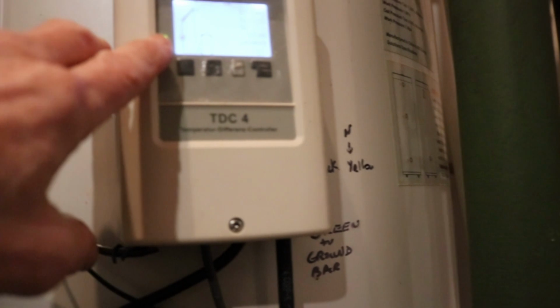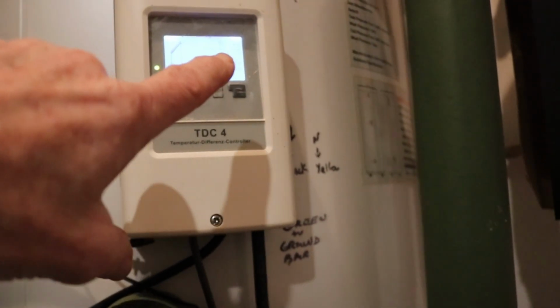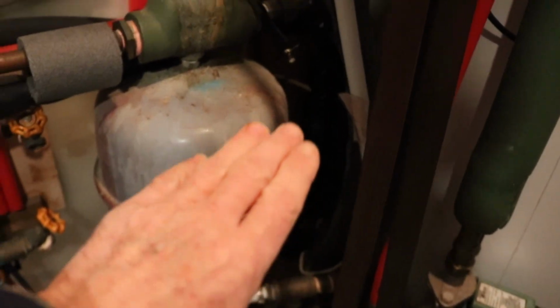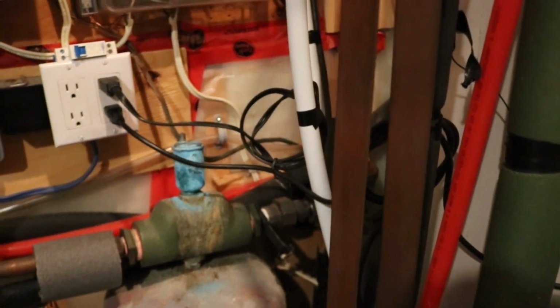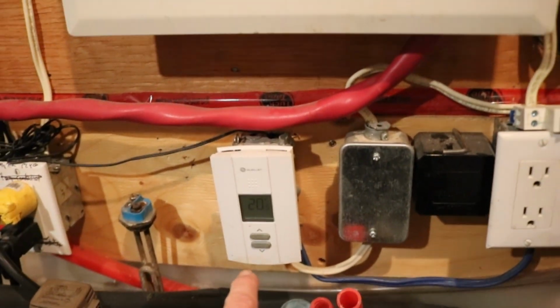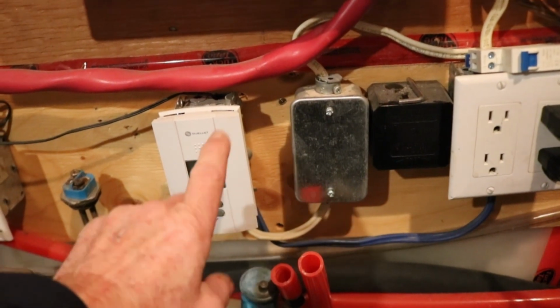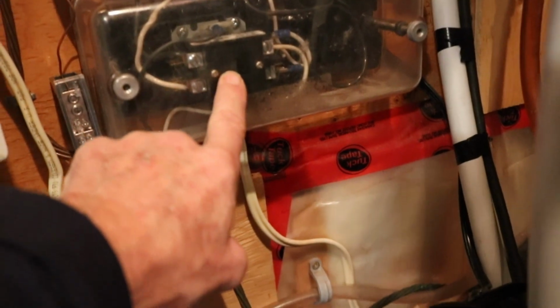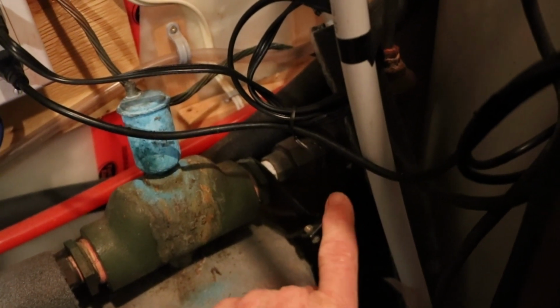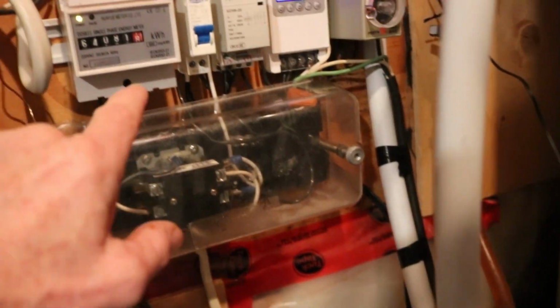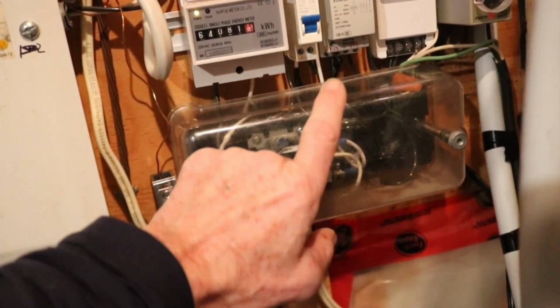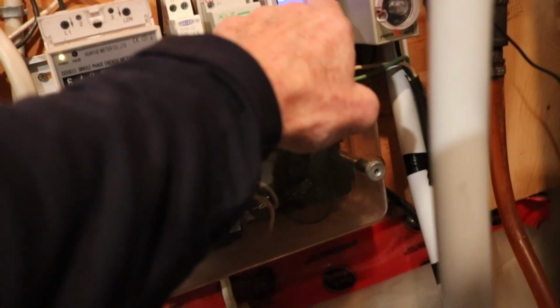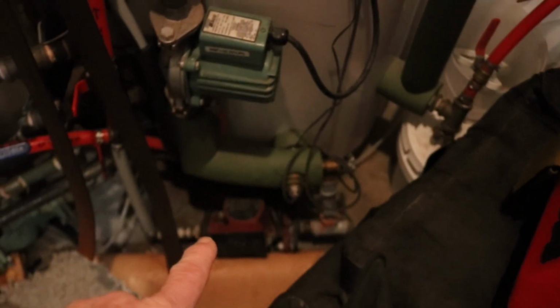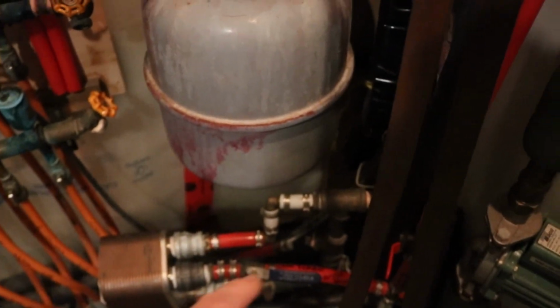So now you can see that this pump started again. The green light's on. And so it's 32, it's pumping through. So this plate heat exchanger preheats my boiler. There's the boiler back in there. So let me show you how this works. When the floor heat thermostat calls for heat, it clicks this relay, which turns on the boiler, heats the floor. Here's a kilowatt meter I have. And then when the temperature here is 24.4, no, when it's 25 degrees, now it's 26, then this pump down here will start and preheat the boiler.